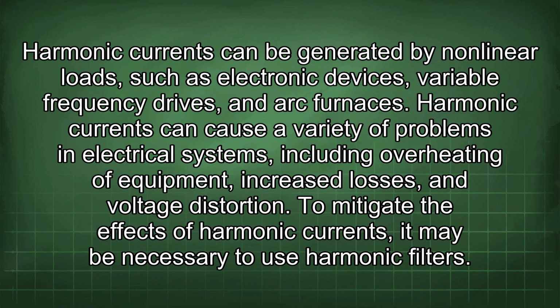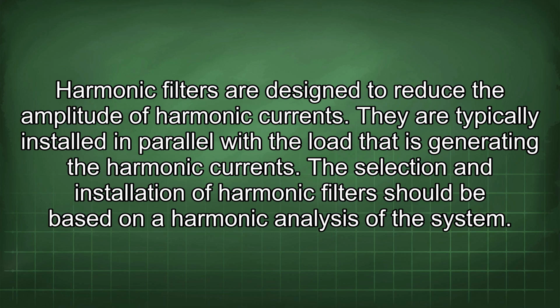To mitigate the effects of harmonic currents, it may be necessary to use harmonic filters. Harmonic filters are designed to reduce the amplitude of harmonic currents. They are typically installed in parallel with the load that is generating the harmonic currents. The selection and installation of harmonic filters should be based on a harmonic analysis of the system.